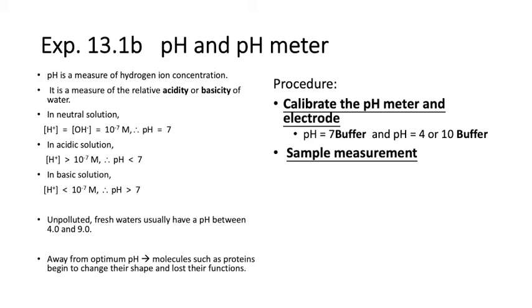During the calibration process, two buffer solutions will be used. For acidic samples, pH 7 and pH 4 buffers will be used. For alkaline samples, during the calibration, pH 7 and pH 10 buffers will be used.